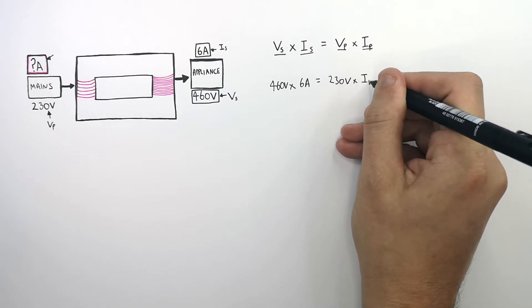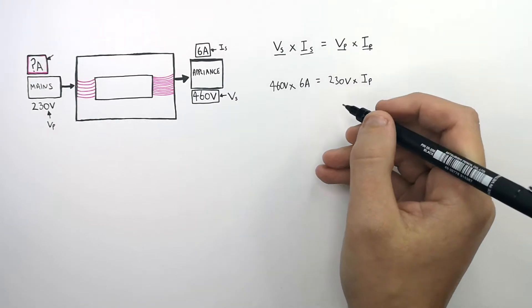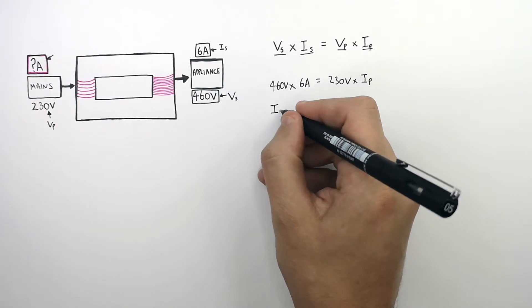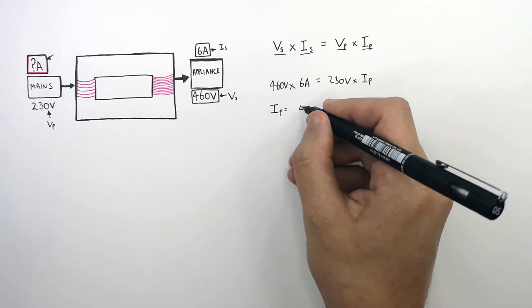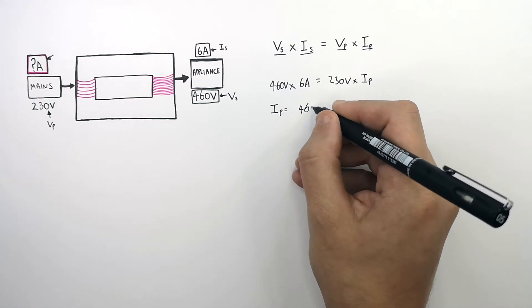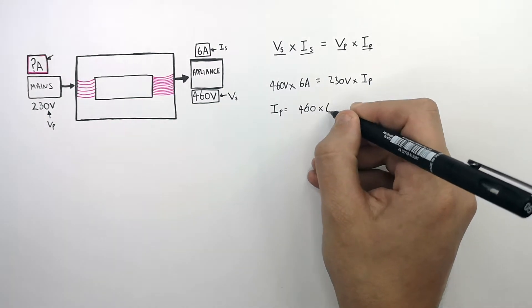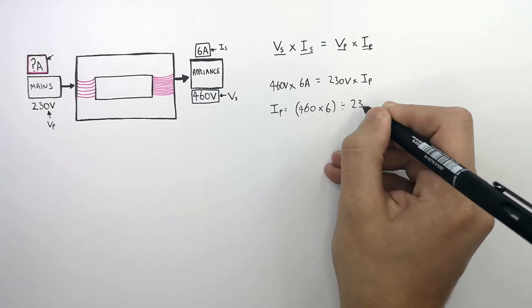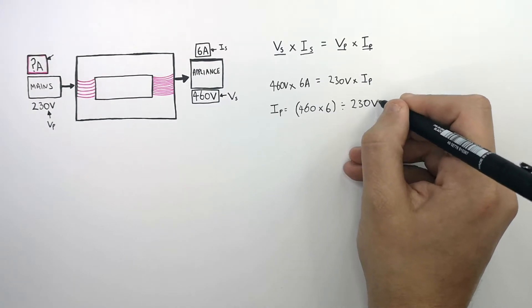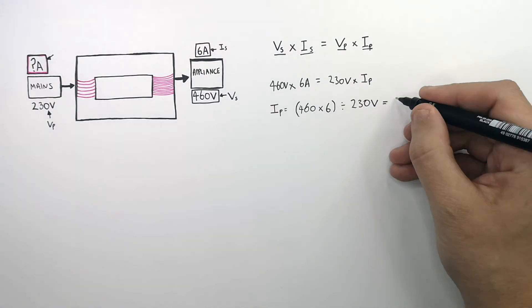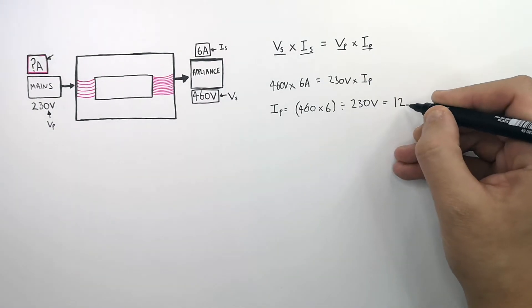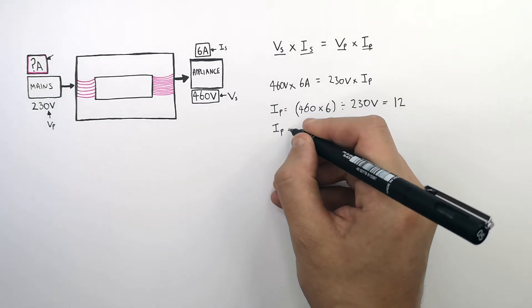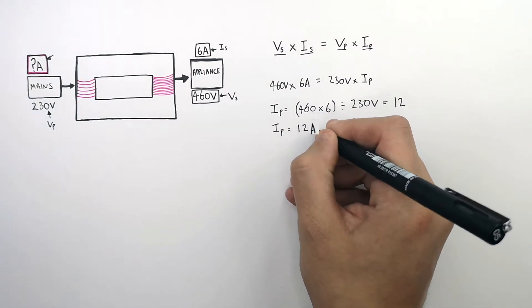We rearrange the equation: IP equals 460 volts times 6 amps divided by 230 volts. That gives us 12 amps. The current in the primary coil is 12 amps.